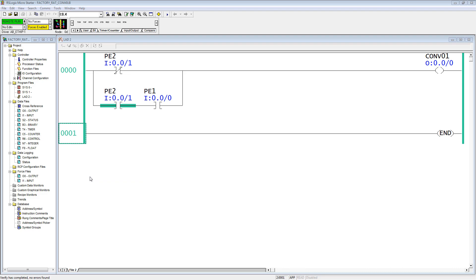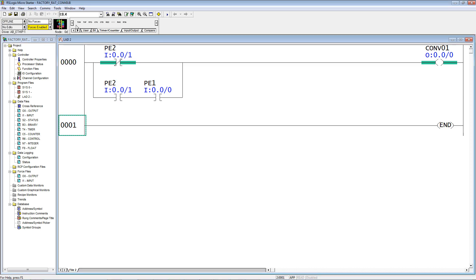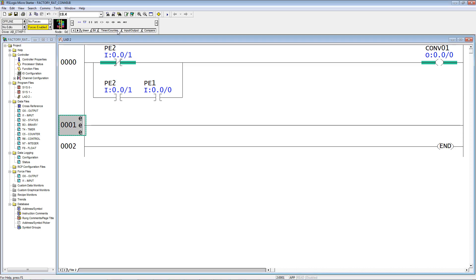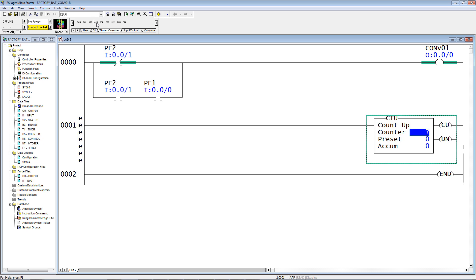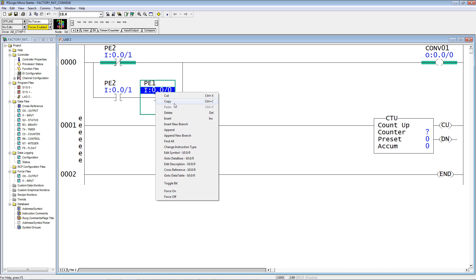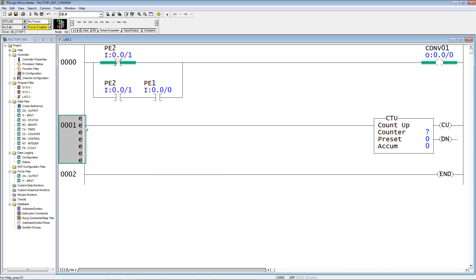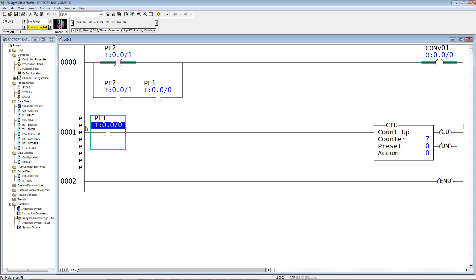I'm going to go offline because it's quicker to add logic offline than online. Add a rung, add a count up instruction. I have to have something to count, photo eye 1, because that's where the carton first arrives. I can copy this, come down here and paste. Whenever photo eye 1 gets blocked, then the counter counts.